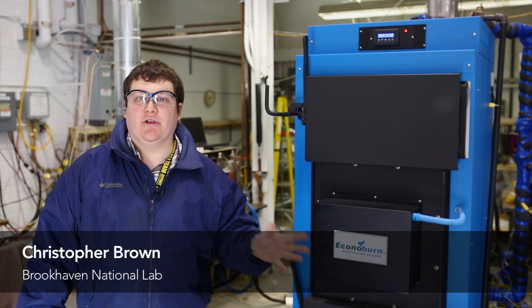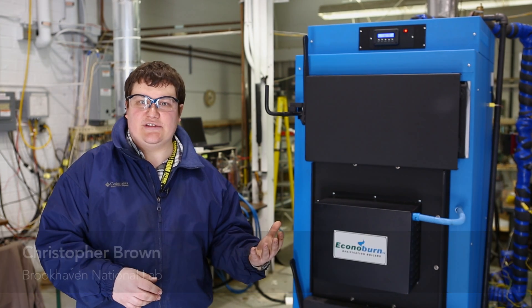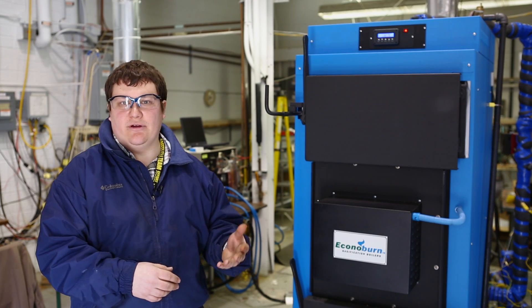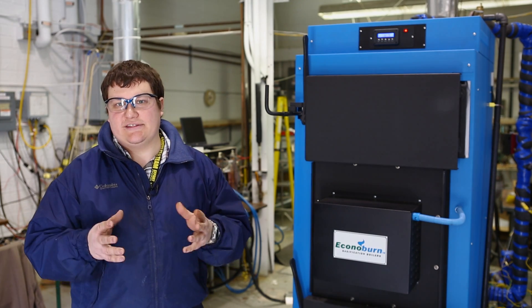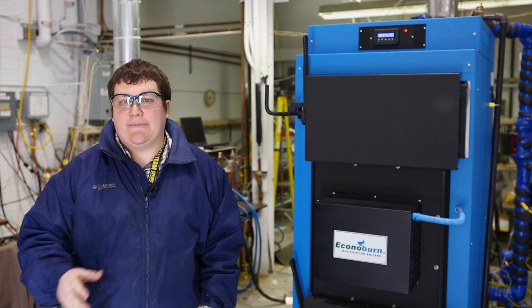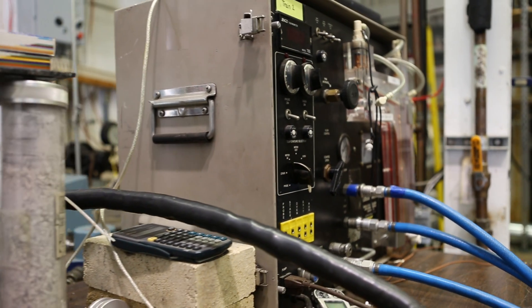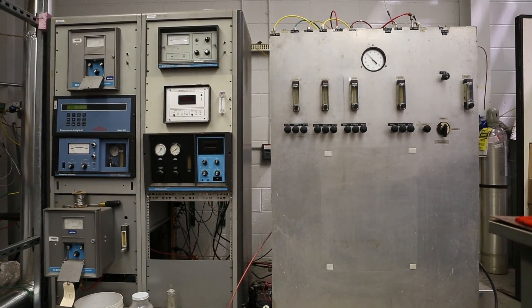We have our Econoburn boiler and we're looking at three stages of testing. We have intermediate stages all the way from the beginning of a test burn through the middle — what we call steady state — through the end phase of the test burn. We're capturing emissions through all three of these phases and looking at how the unit performs over this wide variety of testing.